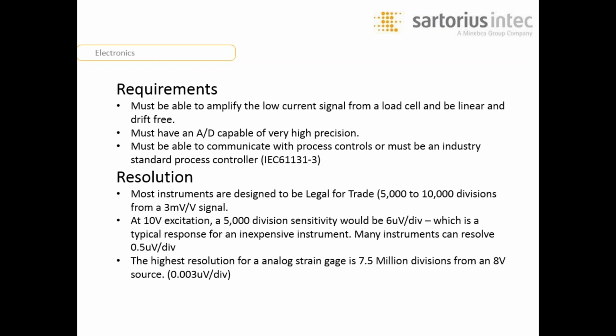Okay, one of the requirements is that the electronics must be able to amplify a very low current signal from a load cell and be linear and drift free. They must have an A to D capable of very high precision. They must be able to communicate with process controllers, or must be an industry standard process controller.